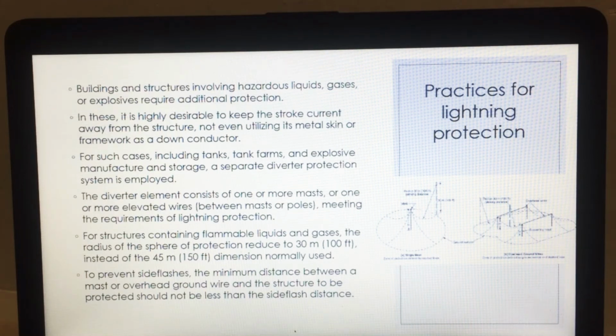The diverter element consists of one or more masts or one or more elevated wires between masts or poles, meeting the requirement of lightning protection. For structures containing flammable liquids and gases, the radius of the sphere of protection is reduced to 30 meters instead of the 45 meter dimension normally used. To prevent side flash, the minimum distance between a mast or overhead ground wire and the structure to be protected should not be less than the side flash distance.